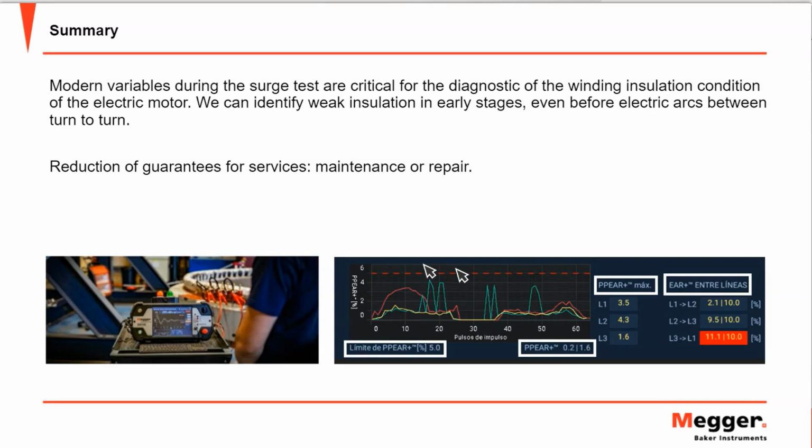So, Mr. Customer, if you want to see the real information, maybe we can test your motor again in 1 or 2 months in order to see if we cross the thresholds. For that reason, I'm not going to give you the warranty, because we are close to the arcs.